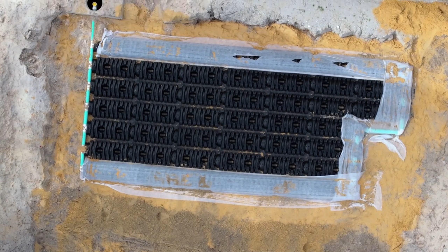Smooth wall pipe is not optional. Corrugated drain tile causes standing moisture and mold. Natural Resources Canada says ribbed pipe holds condensate even on a slope, and that is exactly how people build a swamp under their own house. Do not do it. Use smooth wall. Give water somewhere to go. Keep the air path cleanable.